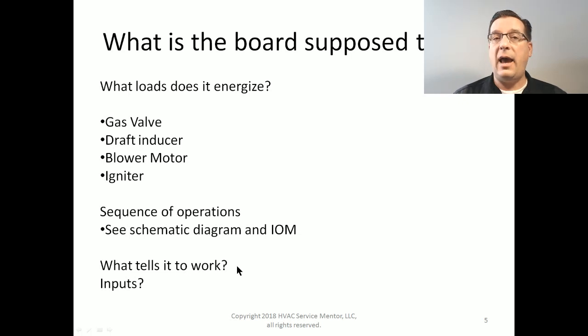The next questions you need to ask yourself and then answer are, what are the things that tell that electronic circuit board to work? How does it know to do its thing and when? For the example of a gas furnace with an integrated control board, the thing that tells it what to do is the thermostat. And how exactly does it do that? What are the inputs that the thermostat gives to the control board? Well, it gives it 24 volts AC on the W terminal. That is an input, that is an operating command. So that's how we want to think about things. We know, what is this thing, what are the loads that it energizes? What is the sequence of operations? And what tells the thing to do it?